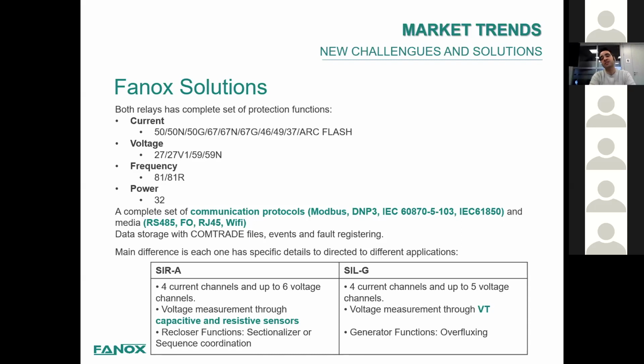And the SIL-G, as it is intended to work with generators, but it can also be very useful in this situation, has 4 current channels and up to 5 voltage channels, through voltage transformers, the traditional voltage transformers. And we also have some functions that are very particular for generators, like overfluxing. But these relays are going to be the subject of the next webinar, and all these applications and the complete definition of them are going to be shown in that webinar.